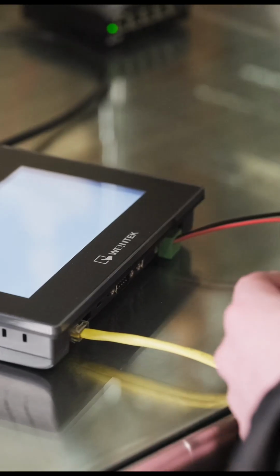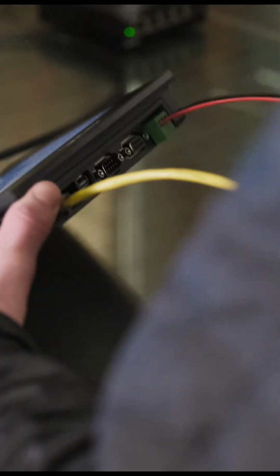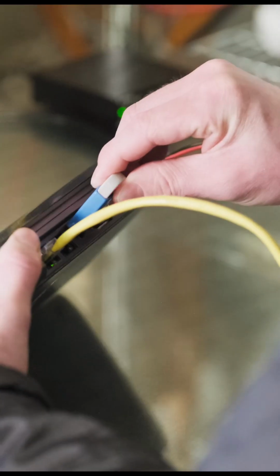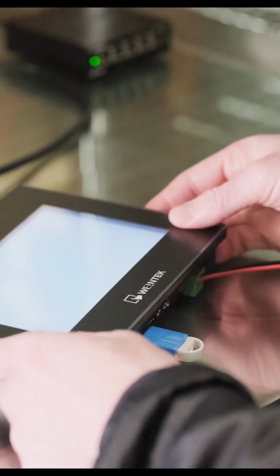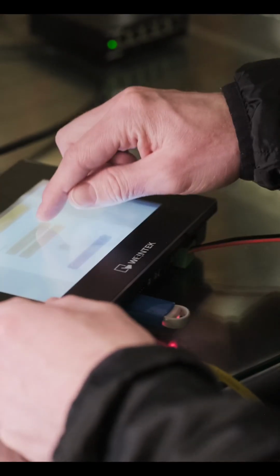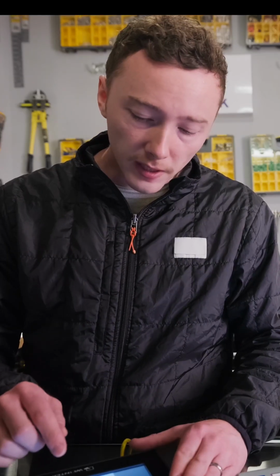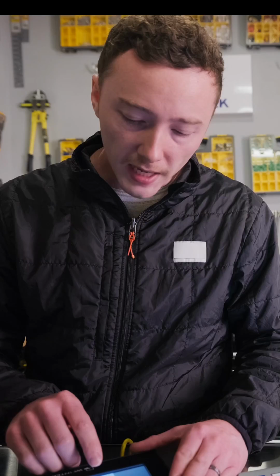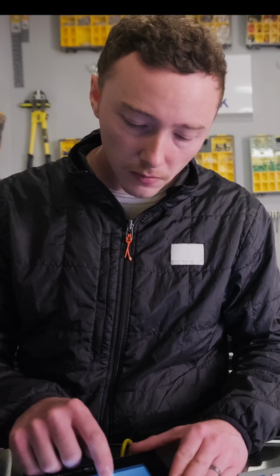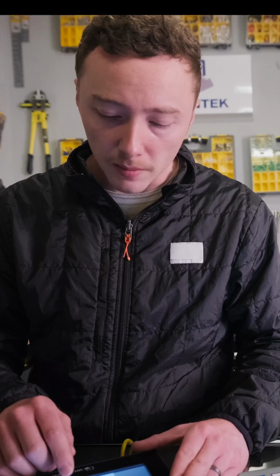When you insert a USB into the HMI, a pop-up menu will display. Within the pop-up menu, you'll want to click the download option. Now, depending on your OS, you may have different options in this menu. In my OS, I have to scroll down all the way to the bottom to see the Codesys project option. If we enable this option, we'll get a folder icon that we can use to browse for our .app file. We can click the download option, and the project will transfer onto our HMI.